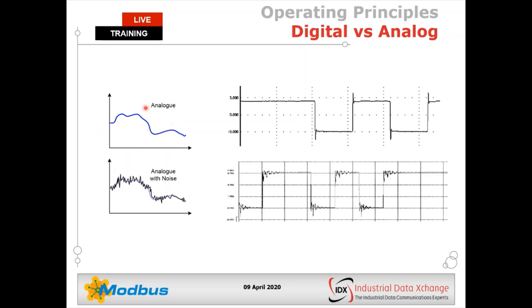The challenge with analog signals is that apart from running a large amount of cabling to each sensor, the cabling can suffer from electrostatic or magnetic interference, line attenuation from cable resistance, or faulty interfaces. Where you have noise injected on the signal — expecting 108°C but reading 120°C — your intelligence system makes decisions based on flawed information, so the process is inaccurate. Instead of running this analog signal all the way to the controller, you could convert it to a digital signal and transfer that digital signal across your plant.